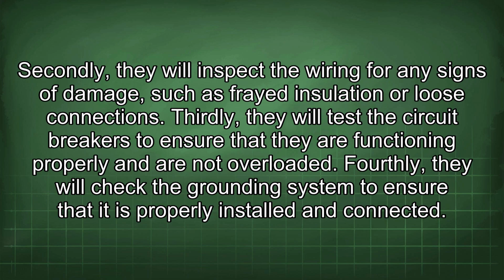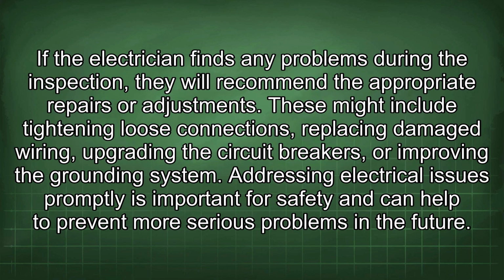Thirdly, they will test the circuit breakers to ensure that they are functioning properly and are not overloaded. Fourthly, they will check the grounding system to ensure that it is properly installed and connected. If the electrician finds any problems during the inspection, they will recommend the appropriate repairs or adjustments. These might include tightening loose connections, replacing damaged wiring, upgrading the circuit breakers, or improving the grounding system.